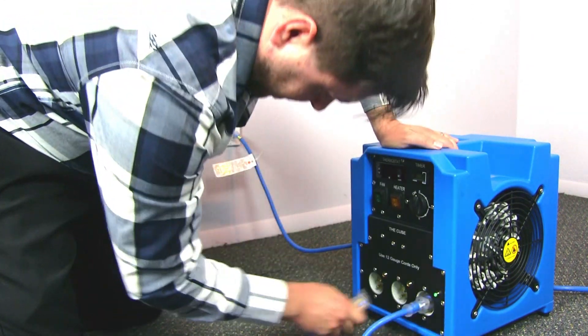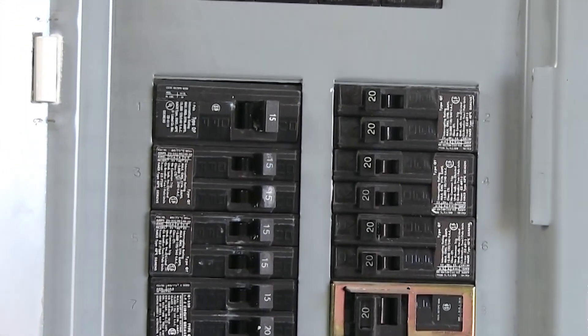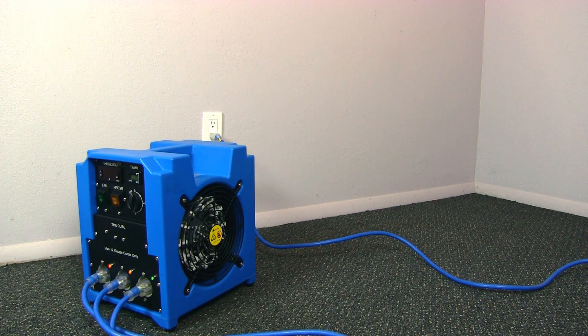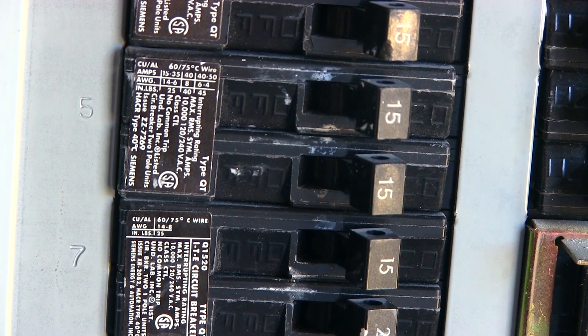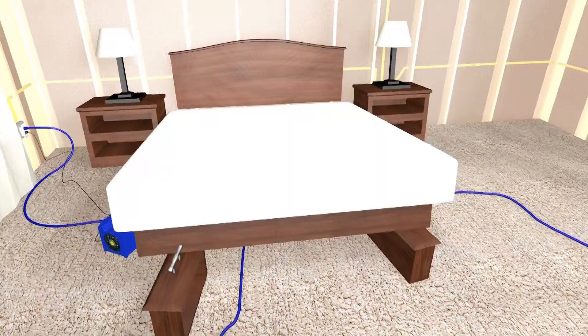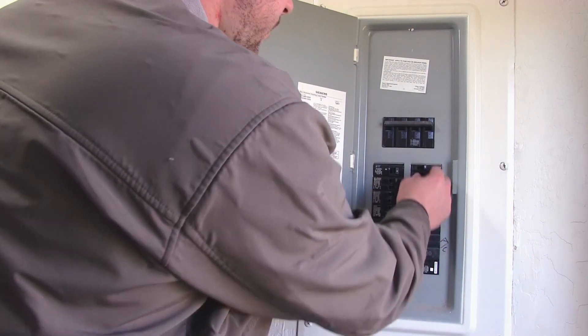The Cube has three power inlets, which are compatible with three standard 120-volt, 15- or 20-amp power outlets found in residential homes and businesses. Keep in mind that each inlet draws 12 amps of power and requires the circuit to be dedicated solely to each inlet, especially when using 15-amp circuits. The heater cannot be fully powered by plugging into the same outlets or in the same room, as these share the same circuit, causing the circuit breakers to trip and shut off the heater.